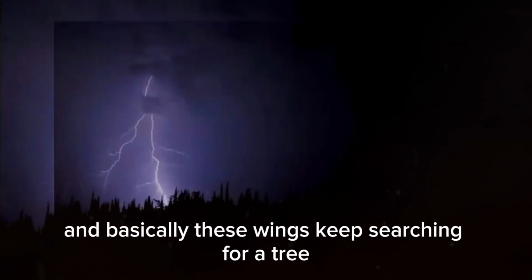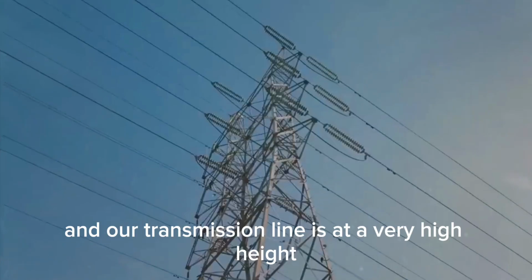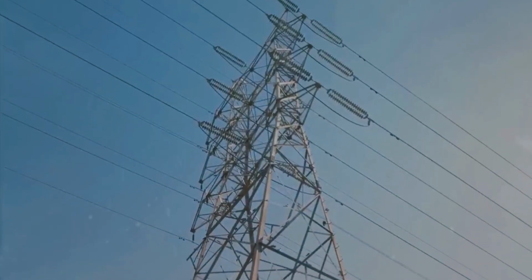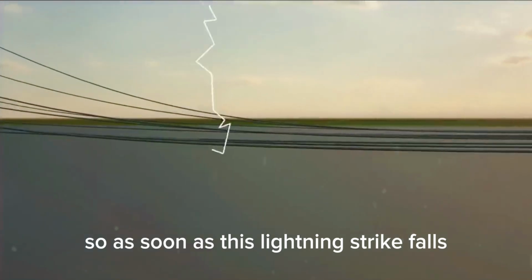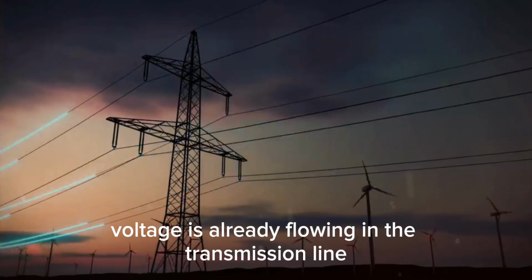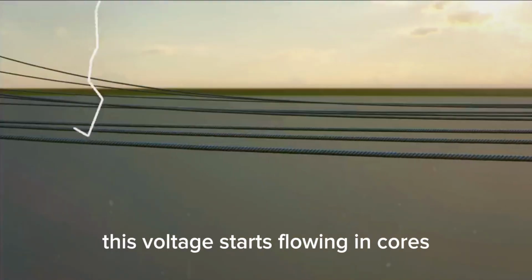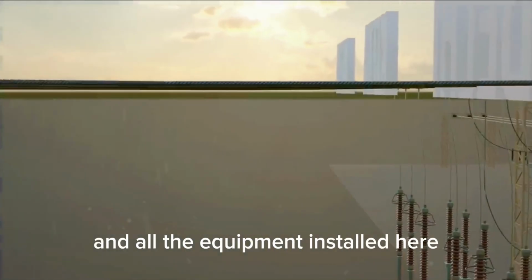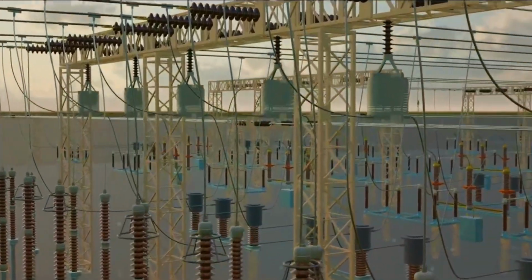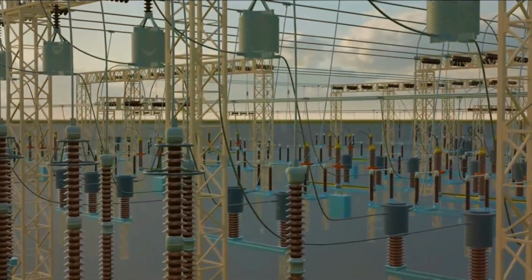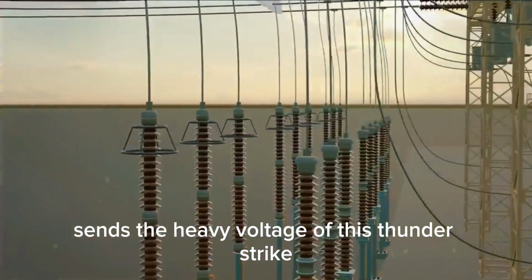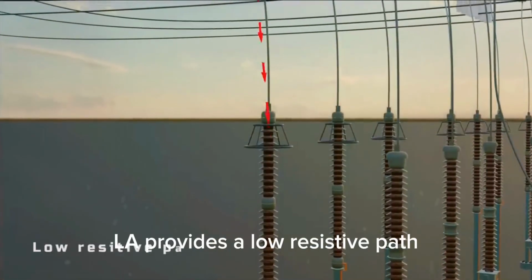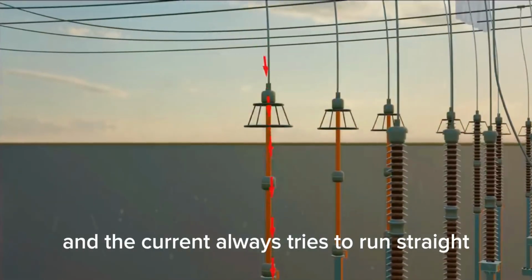When lightning falls from the sky and starts coming down, you must have seen that it has many wings, and basically these wings keep searching for a tree or transmission line, which is at the highest height from the ground, because this lightning has to discharge itself by going inside the ground, and our transmission line is at a very high height. So, as soon as this lightning strike falls on the transmission line, 4 lakh voltage is already flowing in the transmission line, and due to this thunder lightning, this voltage starts flowing in crores, and we have designed the transmission line and all the equipment installed here according to 4 lakh voltage. Not according to crores of voltage. So the lightning arrestor sends the heavy voltage of this thunder strike directly to the ground, because at the time of lightning strike, LA provides a low resistive path and the current always tries to run straight, so it goes to the ground.